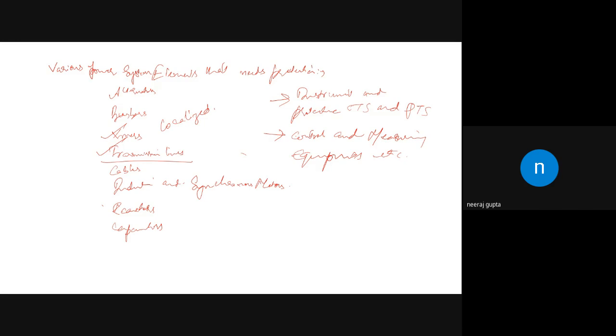While the alternator is a huge rotating mass with mechanical coupling to the turbine and electrical coupling to the power system, the bus bar presents a different scenario. We have the lines connected to it, and simply we use differential protection, taking into consideration the input and the output current and seeing the difference. So generally we use differential protection for bus bar. Each apparatus needs a different kind of protective system, targeted to its unique set of faults and normal operating conditions.